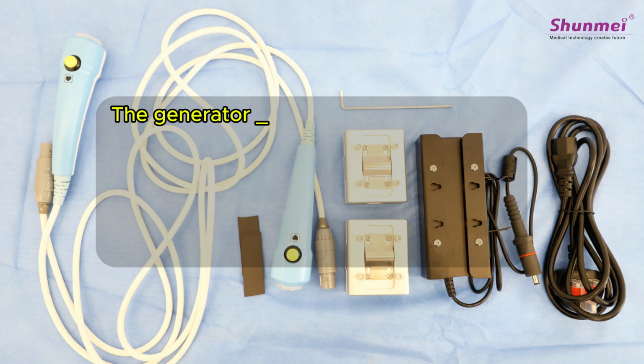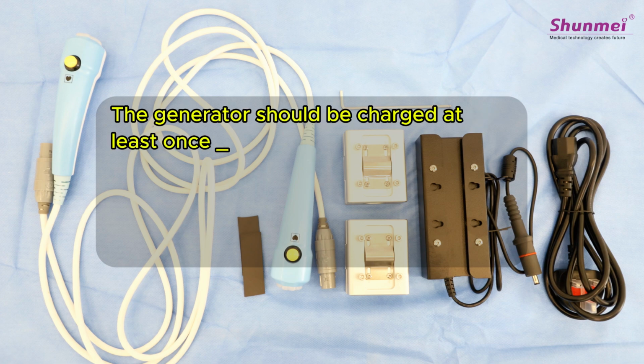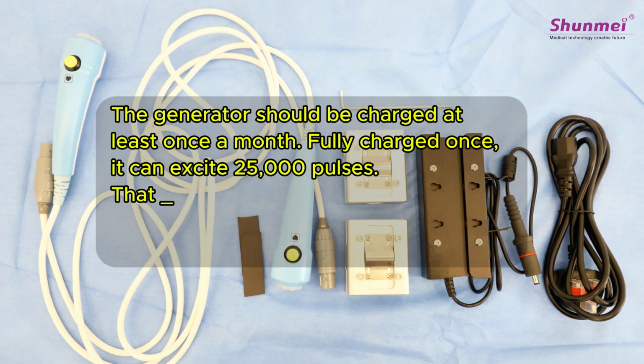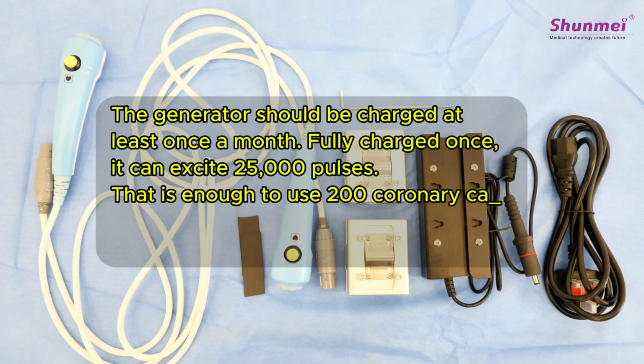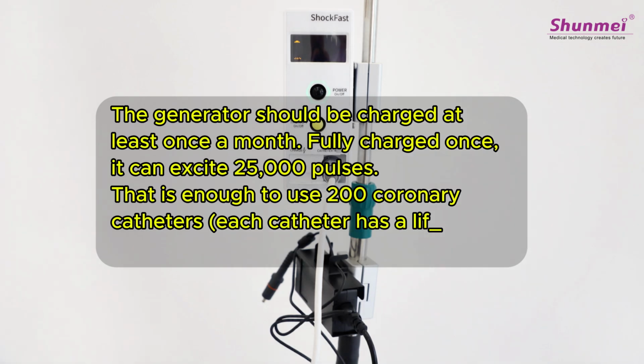The generator should be charged at least once a month. Fully charged once, it can excite 25,000 pulses. That is enough to use 200 coronary catheters. Each catheter has a life of 120 pulses.